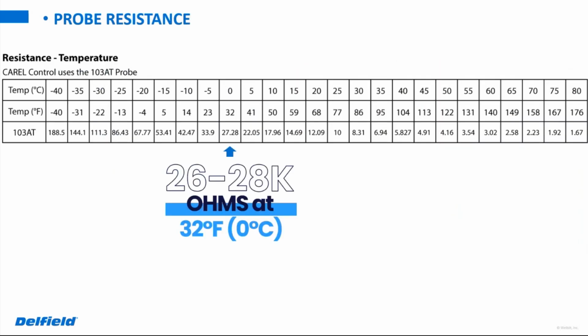As far as resistance goes on these, you can stick them in some ice water, check the resistance, should be about 26 to 28K at 32 degrees. Not all ice water is created equal, so you're going to probably have a little bit of variance, so that's why we allow that bit of a range there.